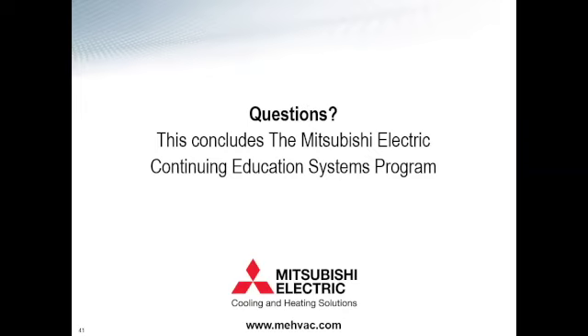Let's see. With any of the indoor units, there were a number of questions about outdoor air supply. Yep. It's a general question, but I think it bears telling the audience that may not be totally familiar with the material. Sure. So all of the Mitsubishi indoor units, other than the wall-mounted unit, can accept outdoor air. So they're going to have various CFM ranges of outdoor air that they can accept.